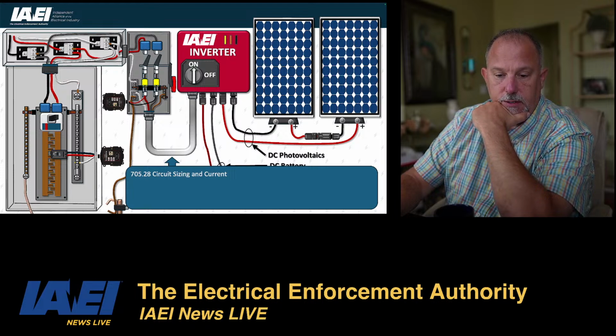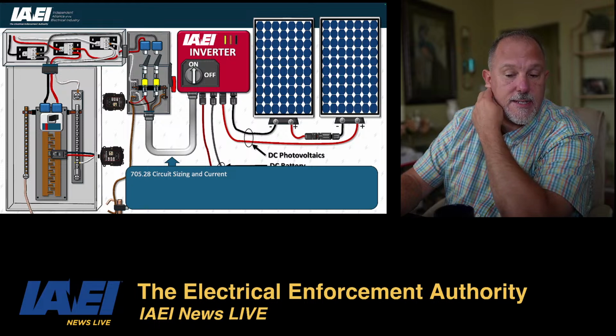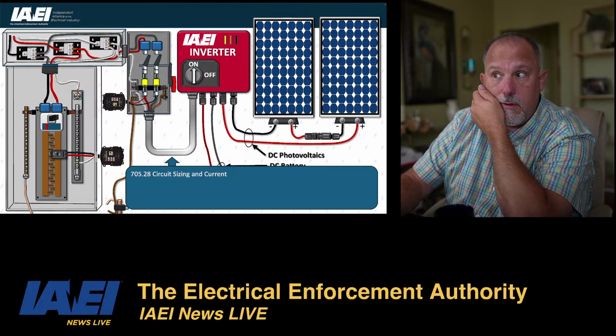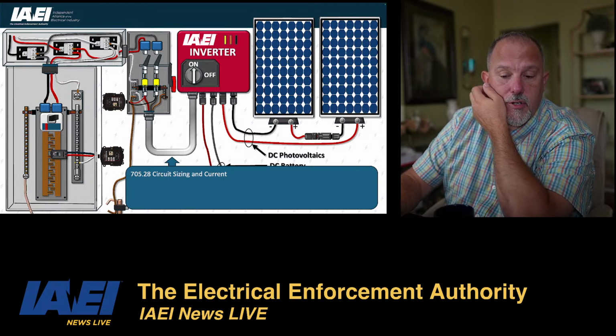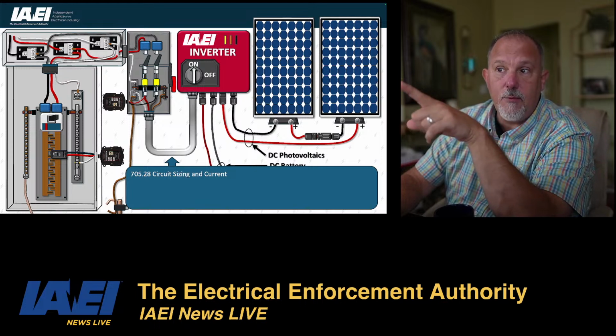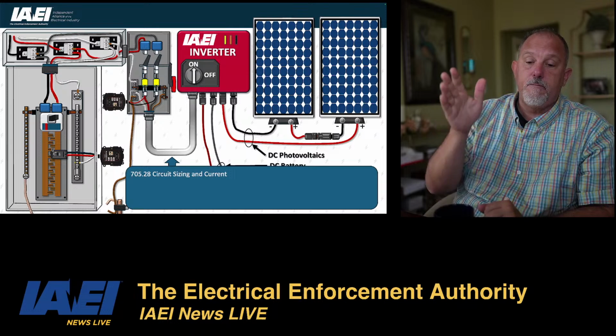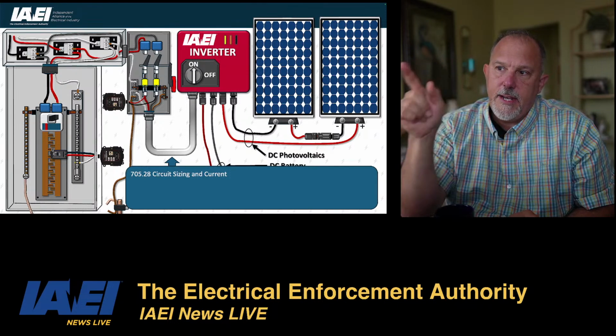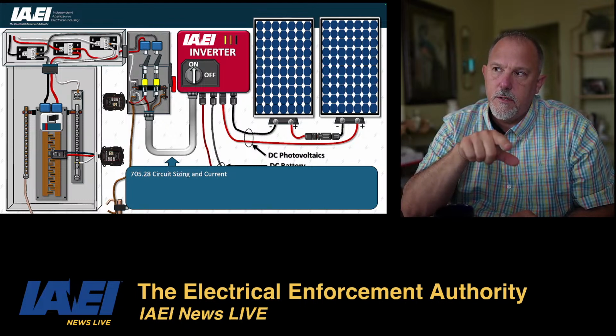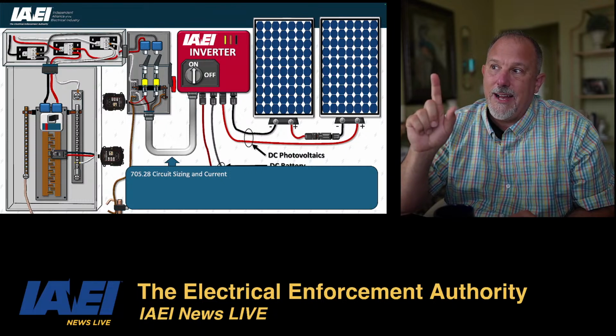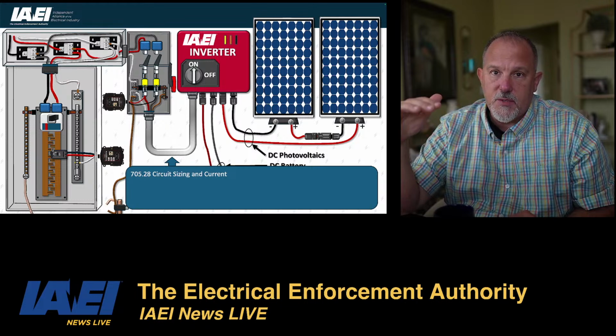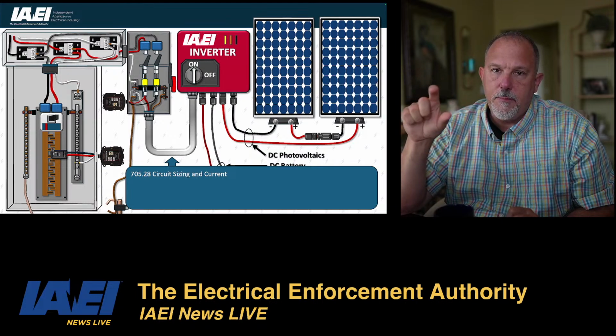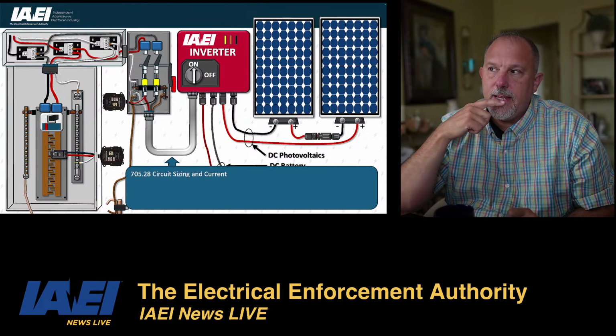Hey, Mr. Electric, I have to scroll down. Perhaps you will have this on a different slide, but it's very common to have the inverter feeding an essential loads subpanel. I'm trying to understand how that subpanel can handle fault conditions. I don't have it on a slide, but I will show it. What I haven't done here is the connection to the load side of the service disconnect. That's 705.12. I have to draw that yet. And then I'll show, to your point, a subpanel that has specific loads, with an inverter supplying power to that subpanel. I can get where that's coming from.